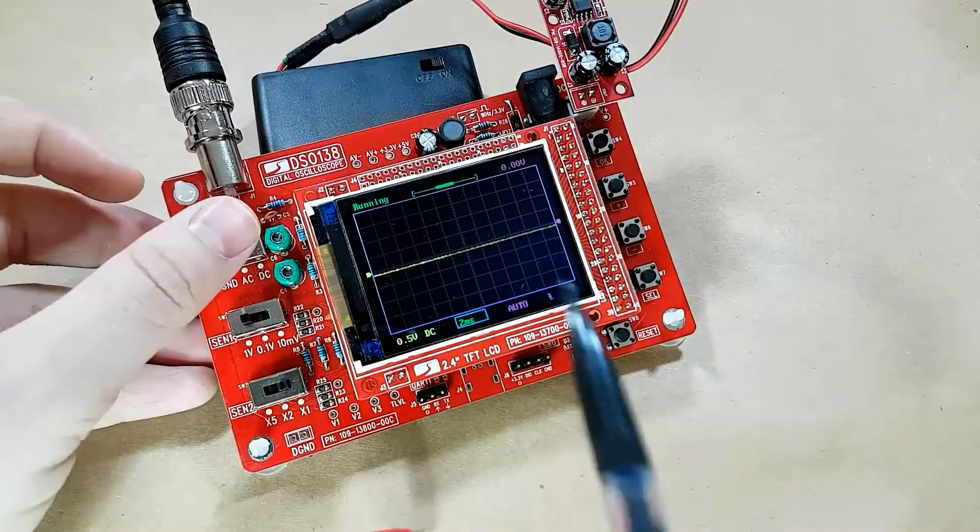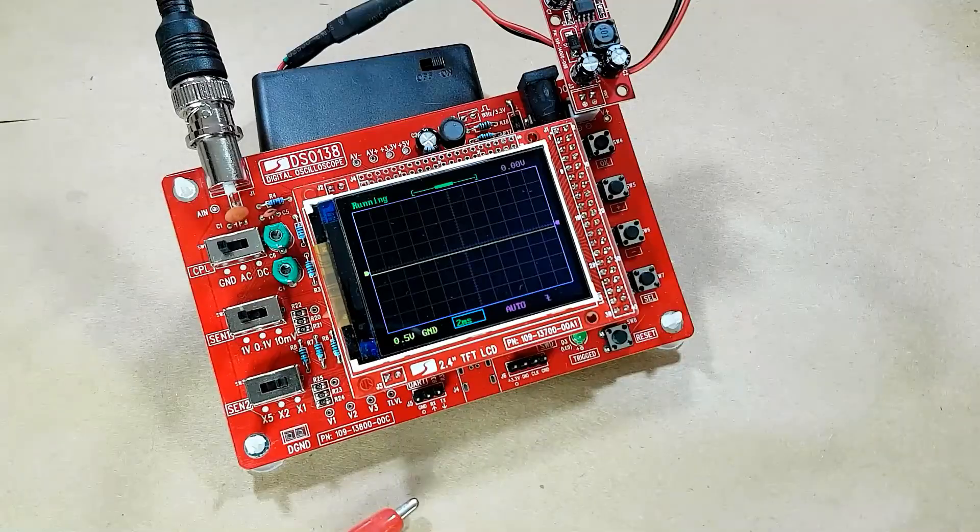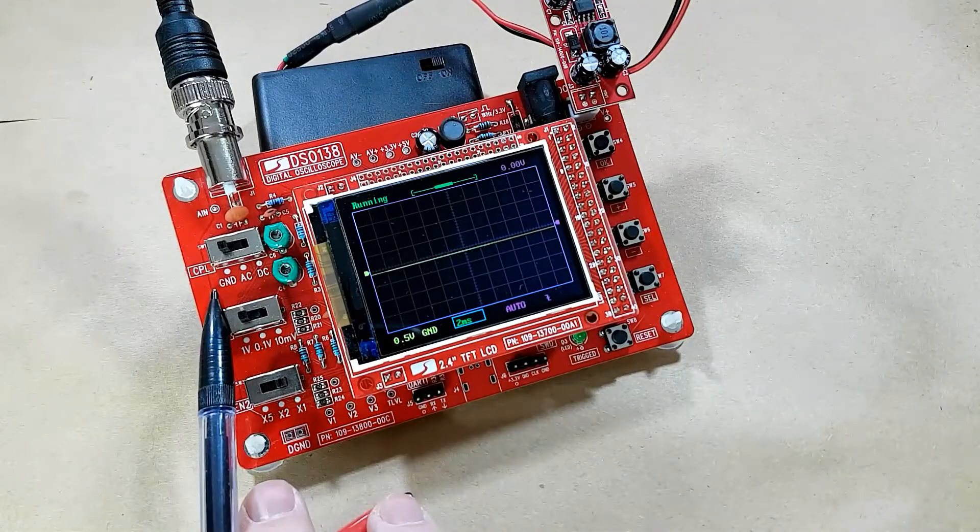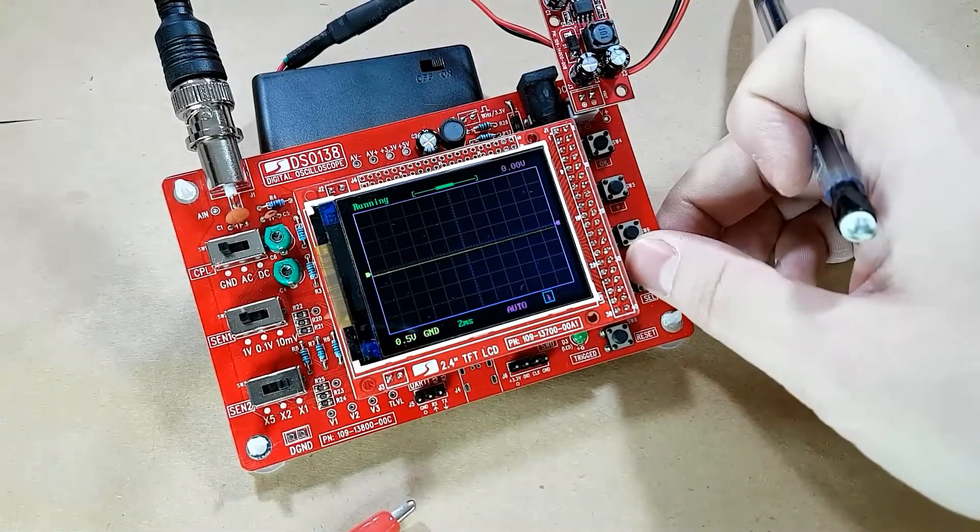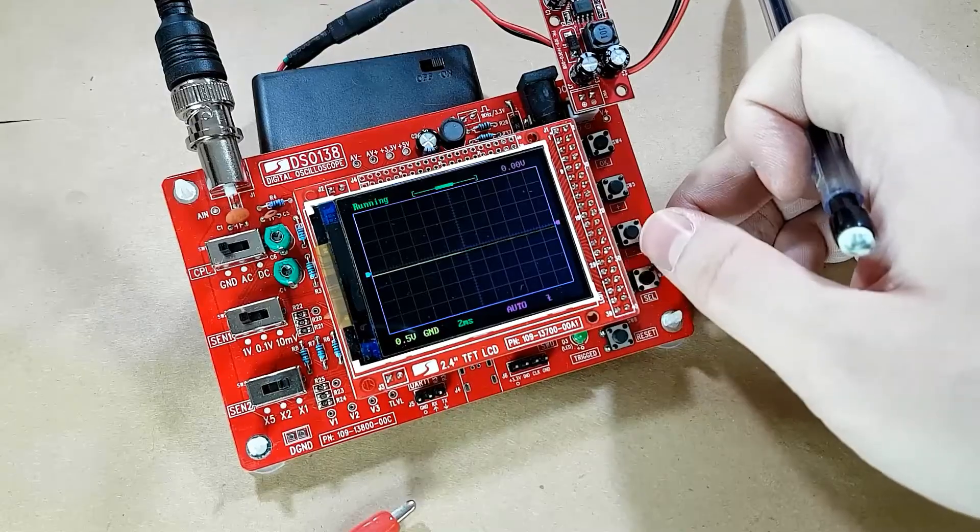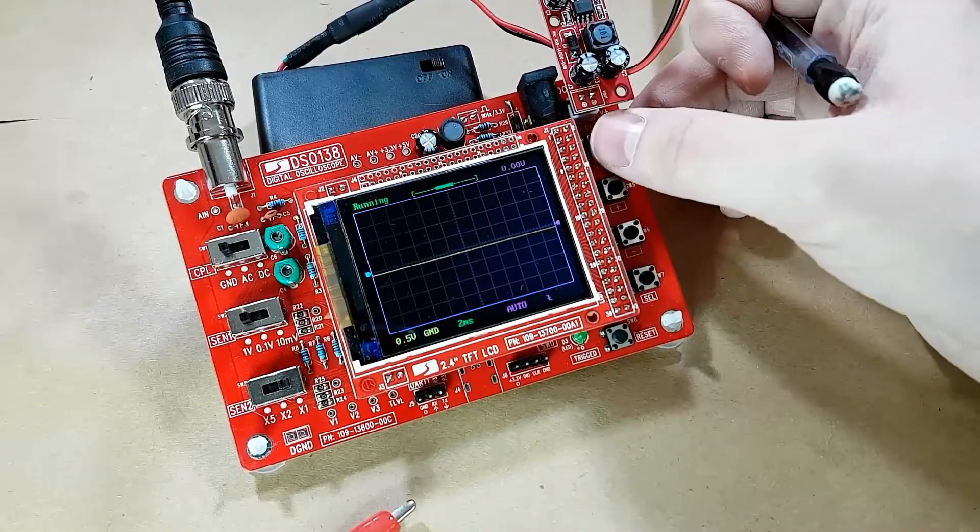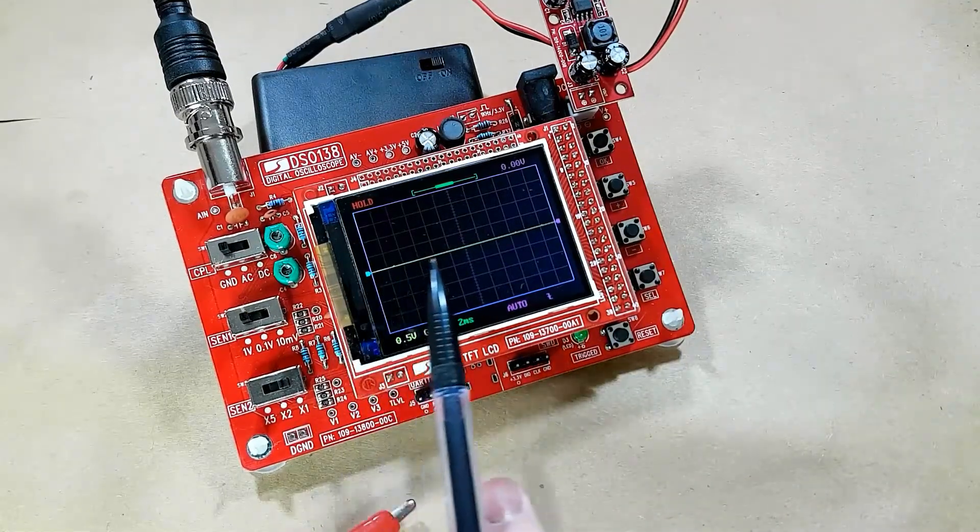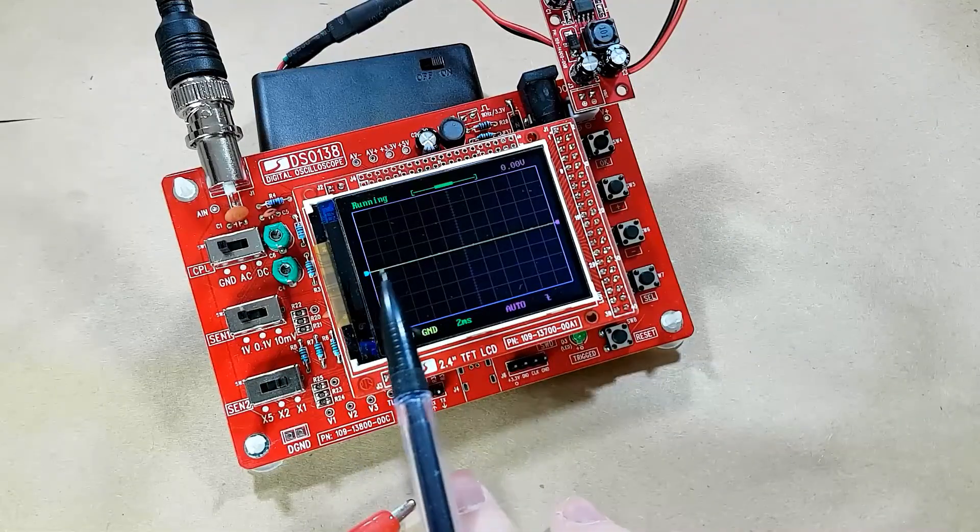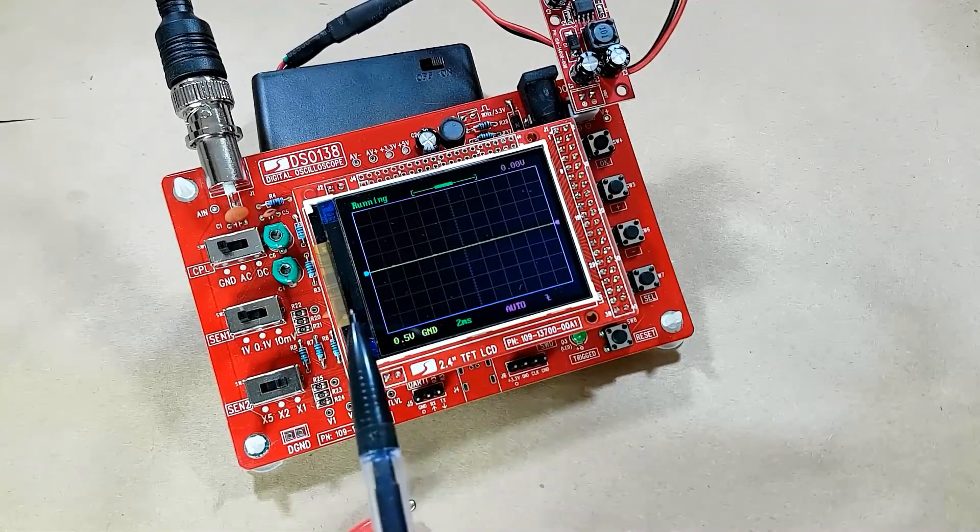Now, to make sure that this line here is where it's supposed to be, we switch the coupling to ground and press the Select button until we get to the vertical selector. Then we hold down the OK button. You can see that just moved the trace up to the selector. So that lined up the trace and the actual vertical selection.